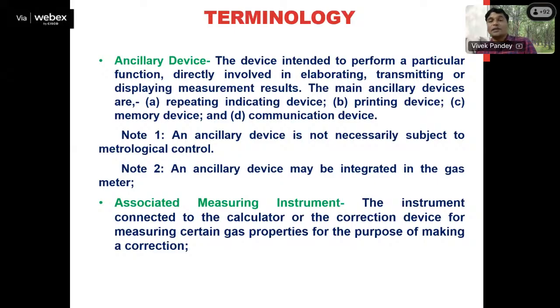Next is the associated measuring instrument. When we talk about the gas meter, it is specifically meant for measuring the quantity of gas, but as I told you, we need some correction devices, so that if there is any variation in temperature, the correction can be applied inside the measuring unit. How will that correction happen? We must have a temperature sensing device inside the gas meter, which can detect the temperature of the gas during a certain transaction.